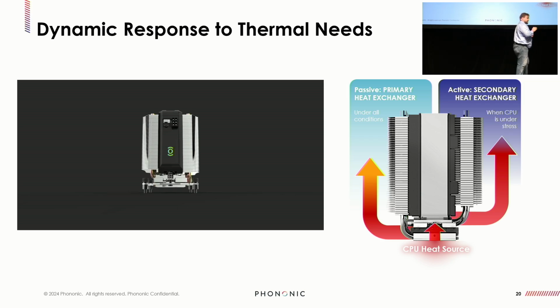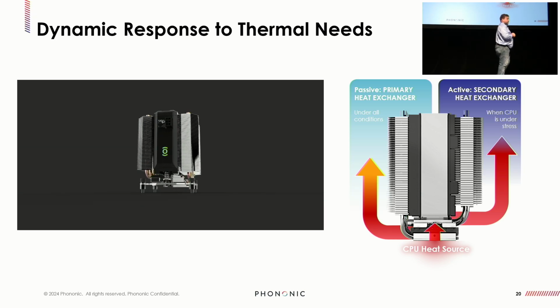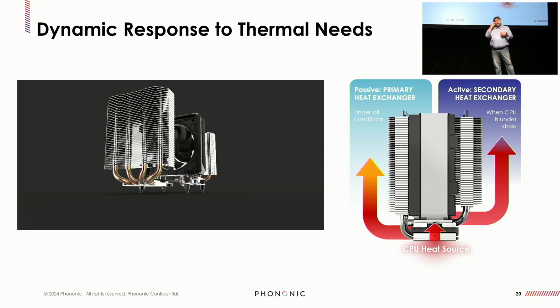Once you reach your thermal limits, the tower transitions from a passive mode to an active mode. The heat pump technology incorporated into this system decouples the base temperature, and therefore the die temperature, and allows the reject temperature to climb. That's MCP delta T for the thermal geeks out there. Delta T allows you to dissipate more energy—higher delta T, more energy dissipated. Same infrastructure, same flow rate, same media, but you can pump more heat out of that system, and you can hold that temperature essentially as long as you want.